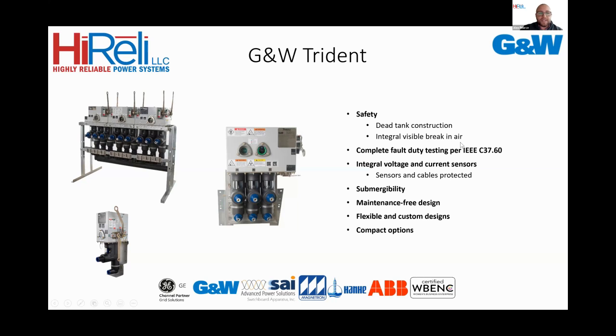So the top left is the compact option if you're stacking multiple ways next to each other. The handles are inset so as not to take up more space. The bottom left is a single phase option for replacing an oil fuse cutout. Then in the center screen, we have a magnetic actuated version that is able to be automated with a mag actuator instead of a motor.